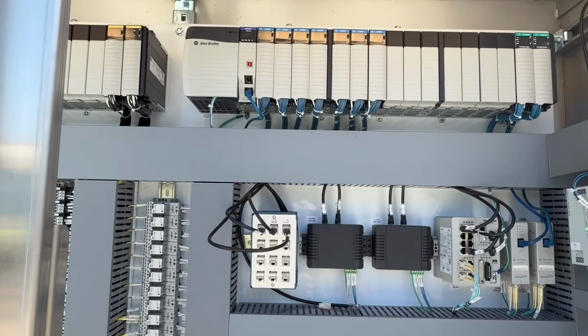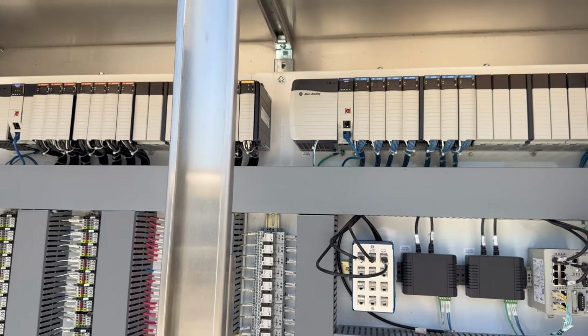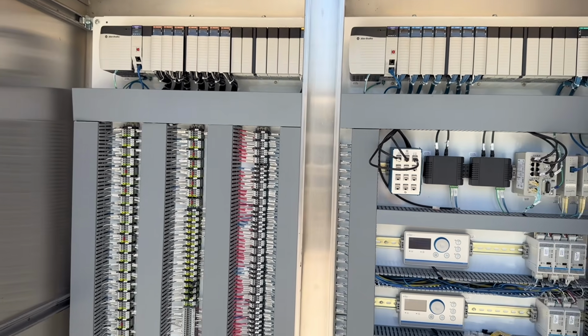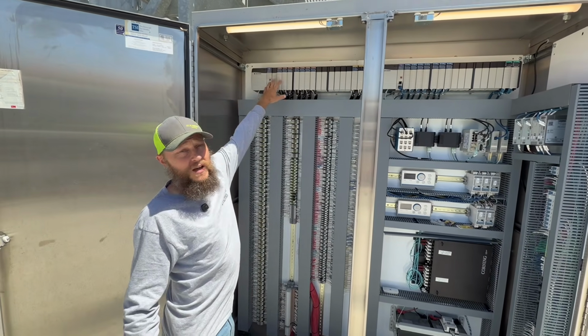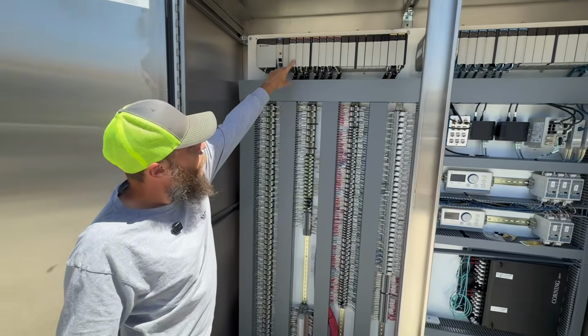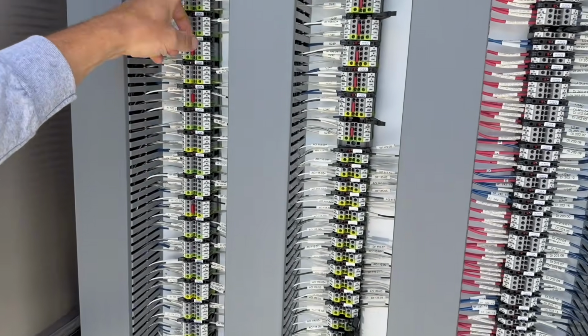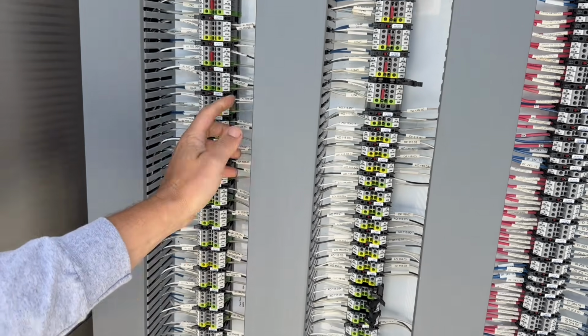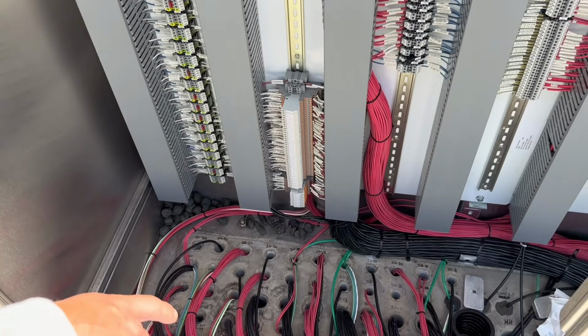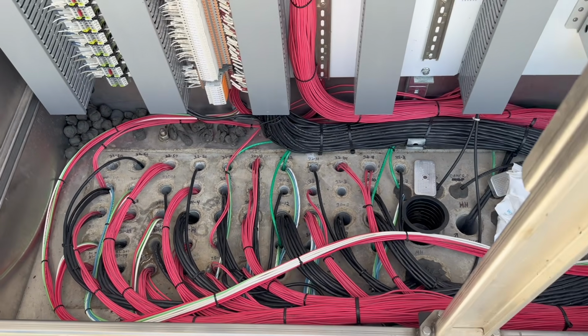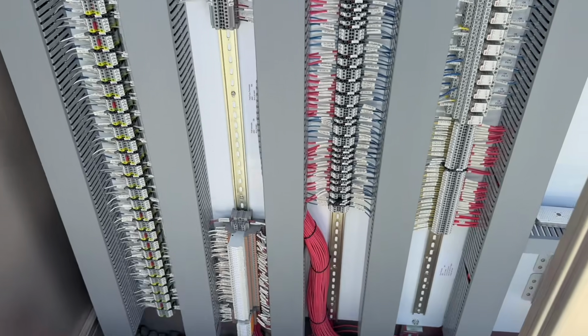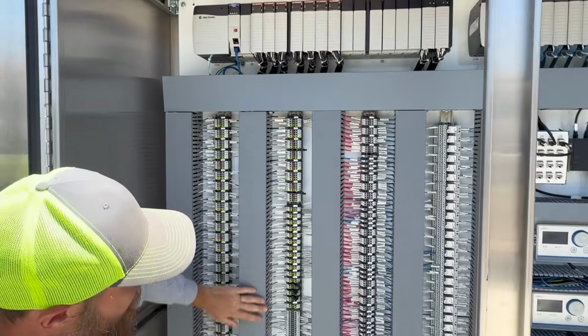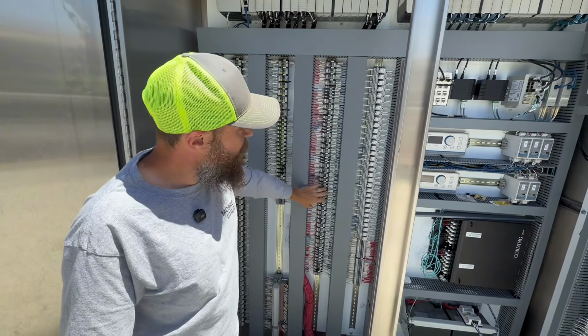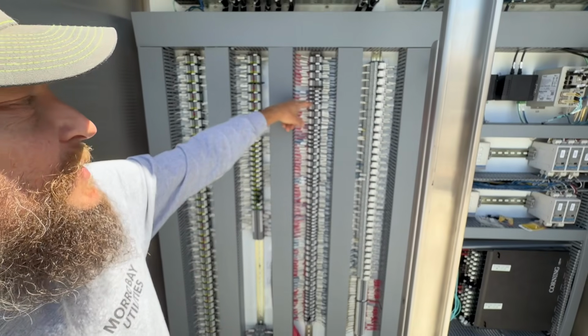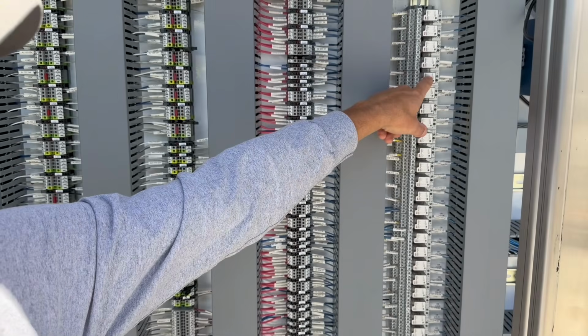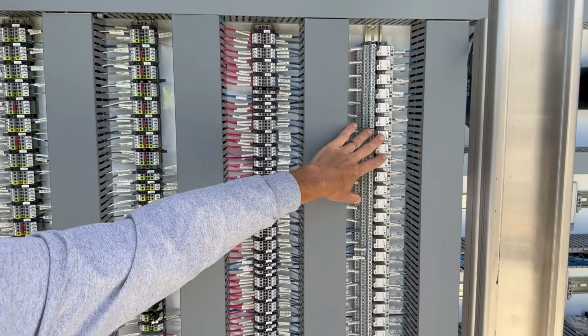It's run or stop. The way this particular panel builder arranged this panel is a great way to organize your I/O. So all the analog inputs are coming in here, and we have wires from the PLC to the terminal blocks, and then the field side wires that are coming from the bottom and from all the devices snake up and terminate here at the terminal blocks. And it's organized the same way it is up top, with your analog inputs, analog outputs, discrete inputs, and discrete outputs. So this is pump states, if it's running or if it's not, and this is telling something to turn on, open, close. These are commands, external.